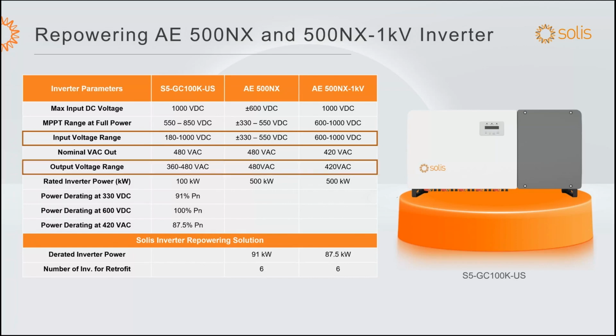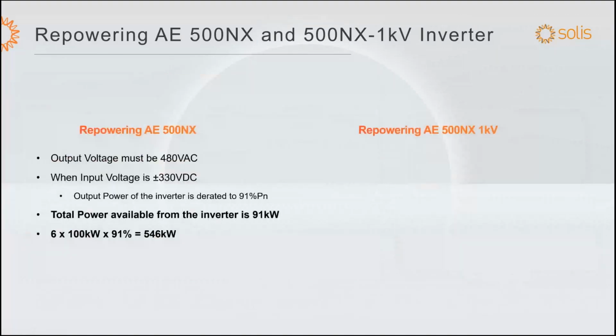And then we look at the AC side. At the AC side, we can cover the 480, and then we can cover the 420 volt of the 500 NX 1 kV. It will take 6 inverters to replace the AE 500NX, and it will also take 6 inverters to replace the AE 500NX 1 kV. And in the same example as previously shown, the reason for derating of the inverter to 91 kilowatt is the 330 volt DC input, and it will be derated to 91 kilowatt.